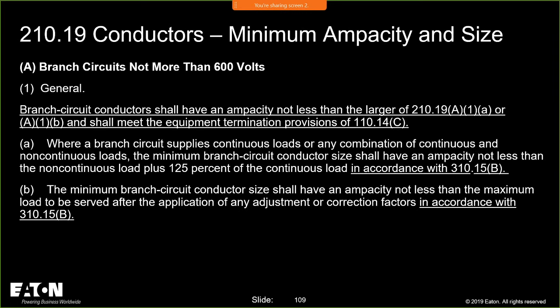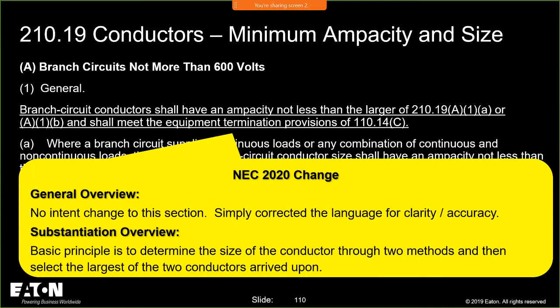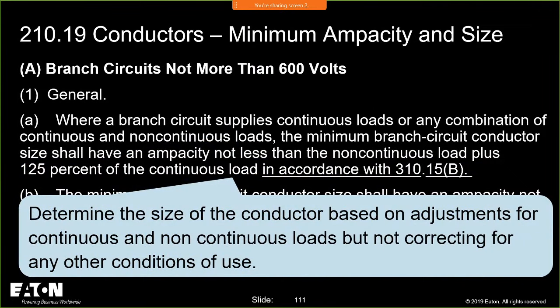And then the second way is that you calculate it without the 125%, but you do the calculation based just on the adjustment and correction factors based upon the conditions of use in accordance with 310.15(B), and then you pick the larger of the two. So we didn't change the intent, but now it reads right, which always bugged me because as I read it before, it seemed confusing, and it was because the language just was not 100% accurate. We fixed that there in 210. We did the same fix in 215. We did both of those.